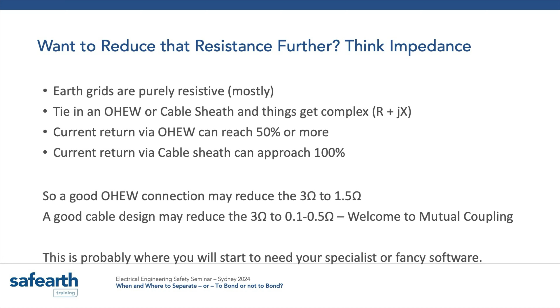and make it safe? Well, the reason is because a 132 kV fault does happen: they accidentally turned the sprinklers on at Daly Street not long ago during a fire test, and they tripped out the 132 kV system, which cascaded, and Sydney tripped out for a little while until they brought it back online again. So there would have been an earth fault, and the cable screens can take about 99.8, 99.9% of the fault current, which means the earth grid and the rest of the distribution system only has to deal with that point something percent of the 50 kA, which makes it a tolerable situation. So it's pretty amazing. That's mutual coupling.